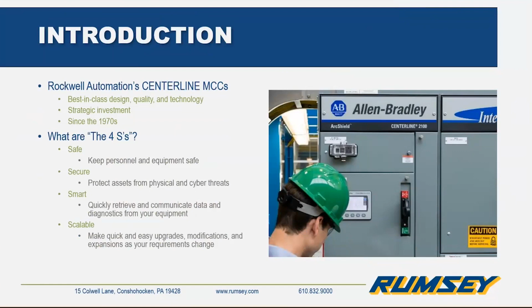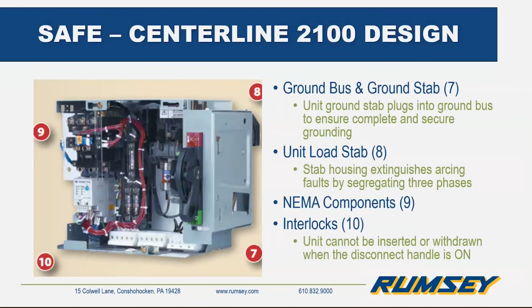Here's a look at the design at a unit or bucket level. First, you have your interlock mechanism that prevents a unit from being inserted or withdrawn when the disconnect is in the on position. A unit load stab in the back helps extinguish arcing faults by segregating the 3 phases. A unit ground stab, number 7 in that picture, plugs into the ground bus, ensuring complete and secure grounding, which is very important.